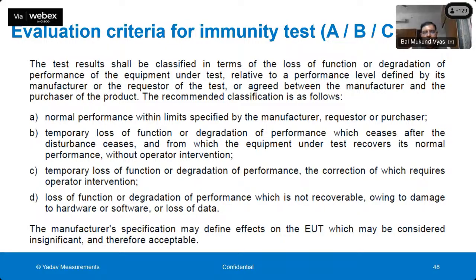After or during this electromagnetic immunity test, various evaluation criteria are specified, which are called A, B, C, and D in various standards. A is normal performance within limits specified by the manufacturer. B is temporary loss of function. So under certain electromagnetic situations, it is allowed that the meter can lose its function temporarily, not permanently. In C, there is temporary loss of function or degradation of performance, the correction of which requires operator intervention. So C and D are not allowed for an electricity meter. For a meter, the evaluation criteria allowed are only A and B.